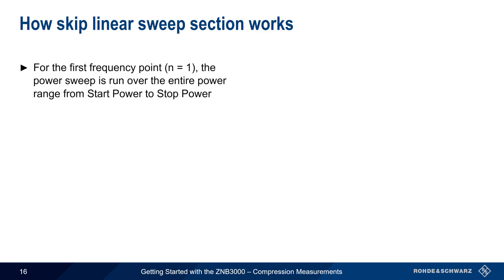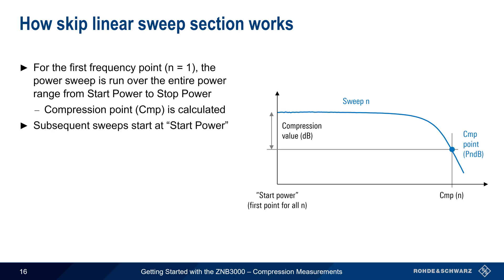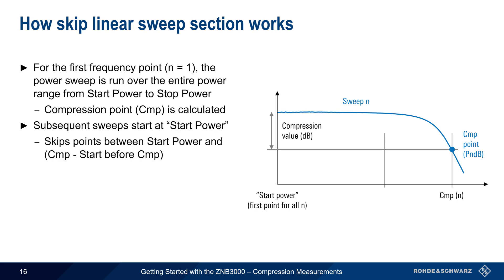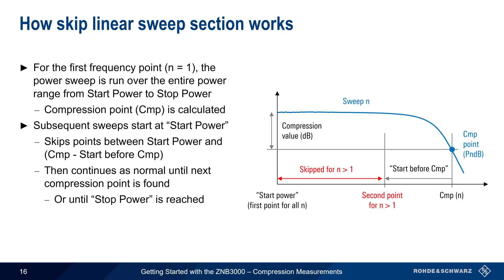For the first frequency point, the compression sweep runs over the entire power range from start power to stop power, or until the compression point is found. Subsequent power sweeps will start at the start power but will then skip all sweep points between the start power and a defined input power — specifically, the compression power minus the user-entered value for Start Before Compression. The power sweep then continues from this second point as normal, until the next compression point is found or until stop power is reached. This process is repeated for each frequency point, with the goal of reducing overall measurement time.